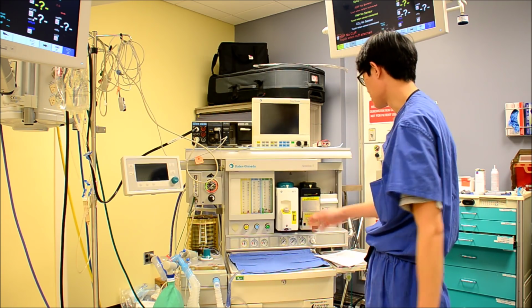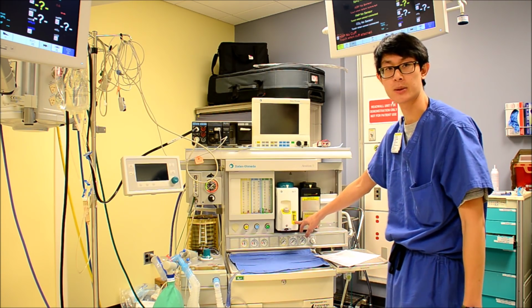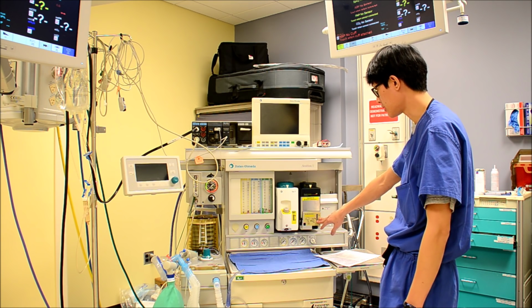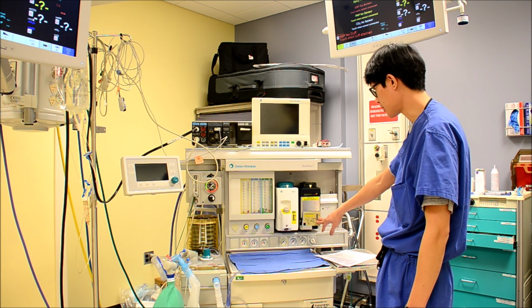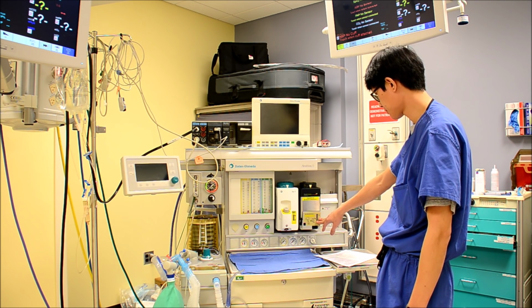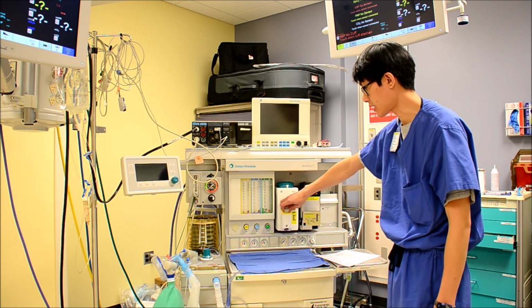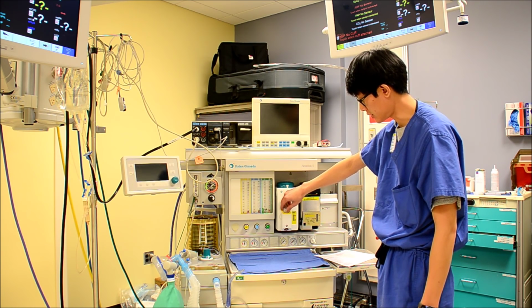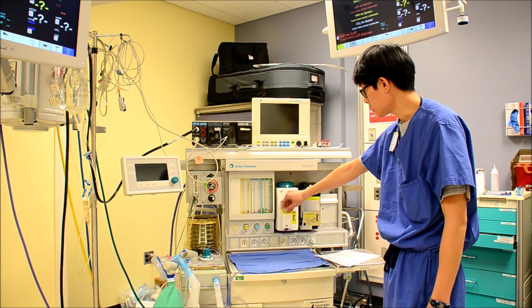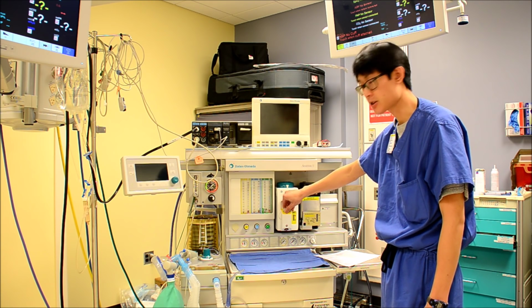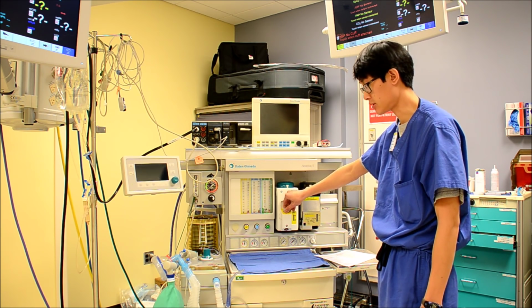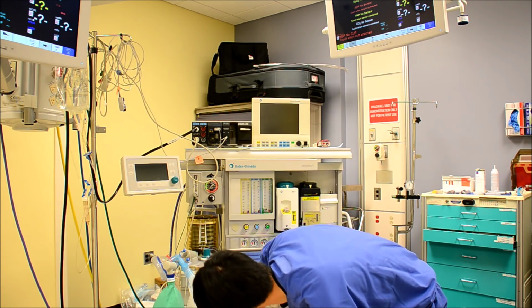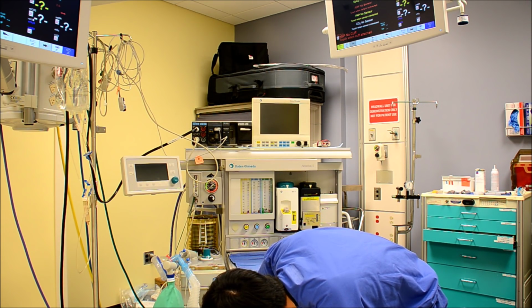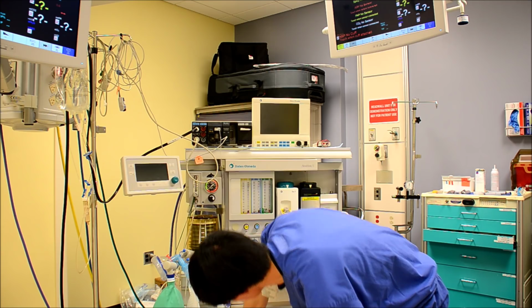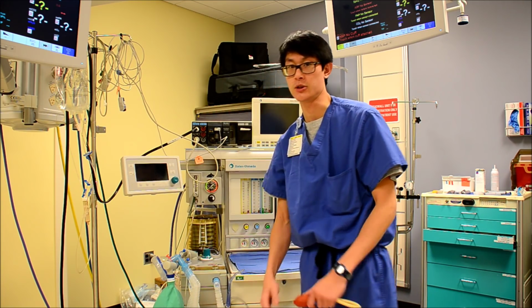The next thing to do is to make sure that if you're going to go ahead and fill your vaporizers, this will be a good time to do it now, because once you perform your low pressure checks and you crack one of these valves open and you don't securely tighten it, then you've already broken the system of the low pressure system. This would also be a good time to check the color of your CO2 absorber. If it needs to be changed, this would be a good time to do it before you check your low pressure system as well.